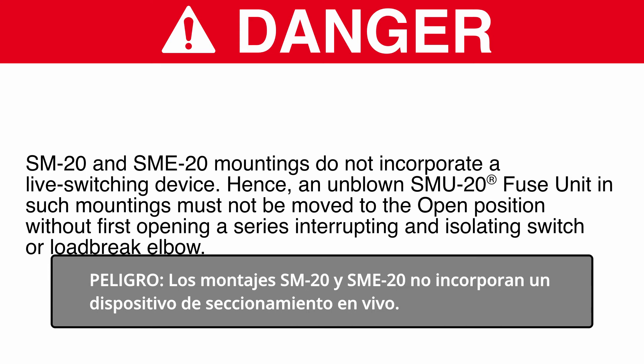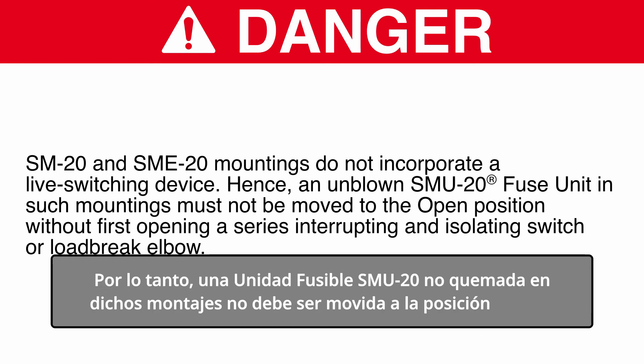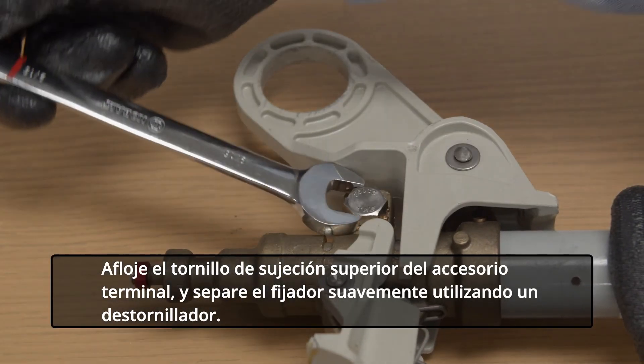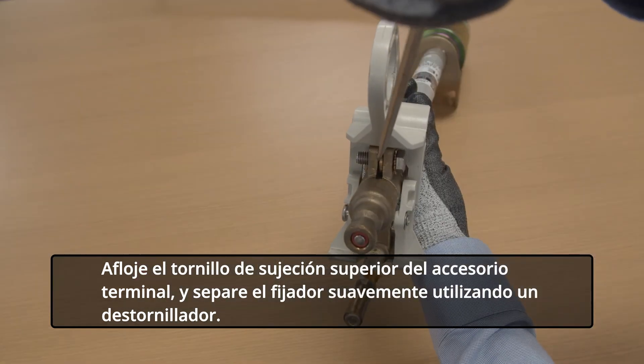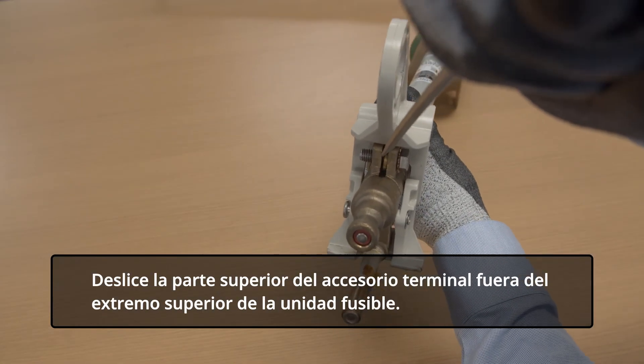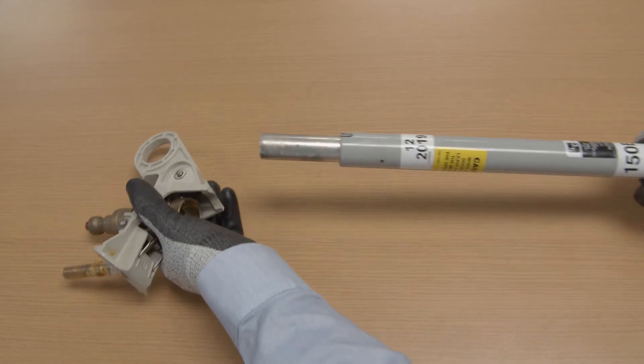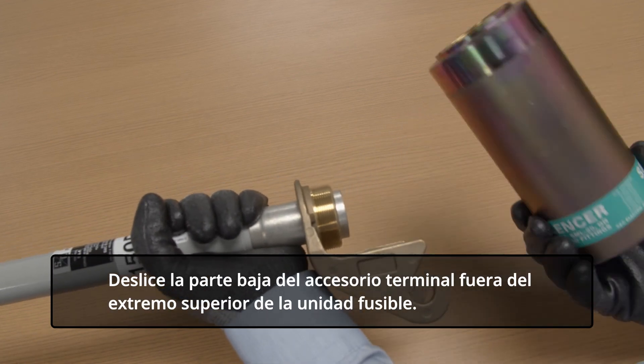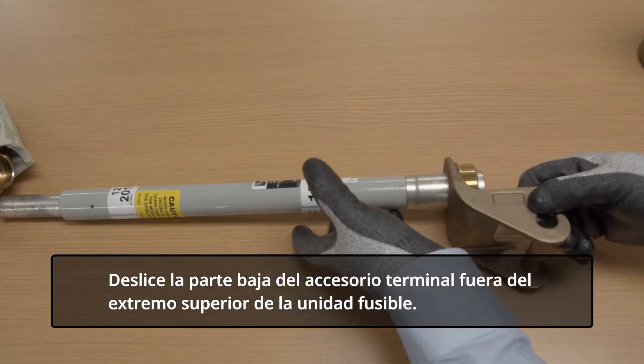SM20 and SME20 mountings do not incorporate a live-switching device. Hence, an unblown SMU20 fuse unit in such mountings must not be moved to the open position without first opening a series-interrupting and isolating switch or loadbreak elbow. Loosen the upper-end fitting clamp screw and pry the clamp apart slightly using a screwdriver. Slide the upper-end fitting off the upper end of the fuse unit. Then, unscrew and remove the silencer. Slide the lower-end fitting off the upper end of the fuse unit.